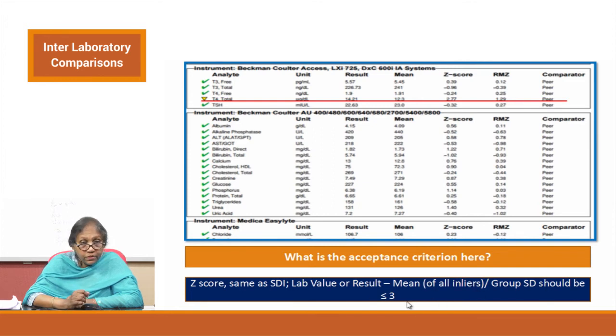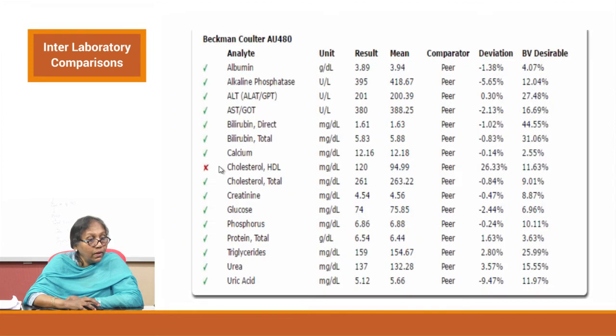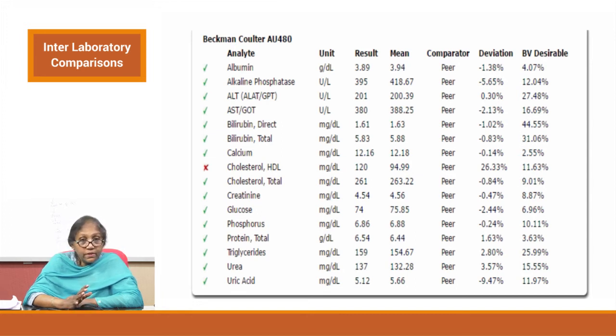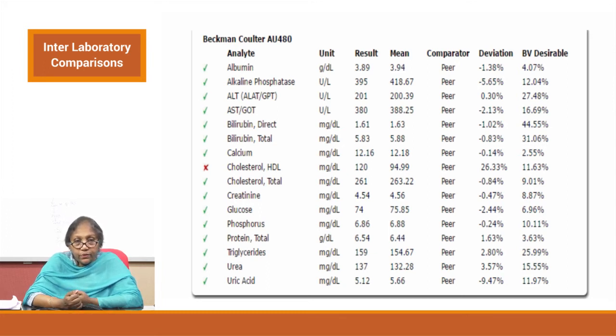Another type of report compares your deviation to what is desirable according to biological variation. An outlier is marked showing 26% deviation for HDL cholesterol, while BV desirable is 11.63% — this immediately draws attention and prompts corrective action. These are additional pieces of information your provider might give you, so make the best use of your EQAS program.